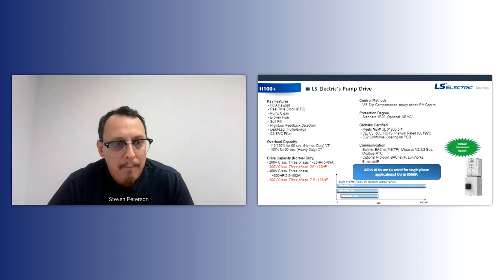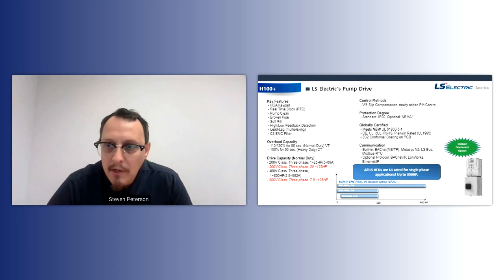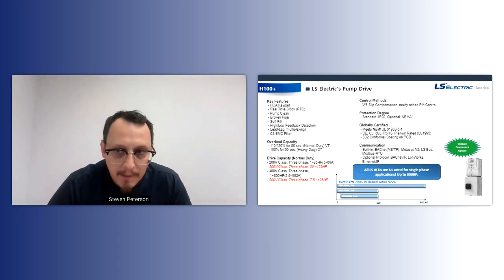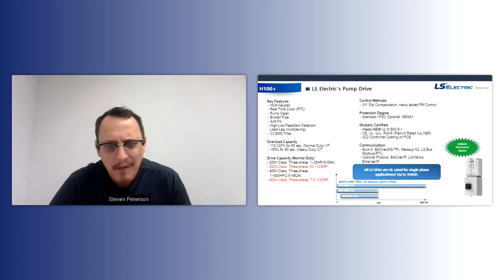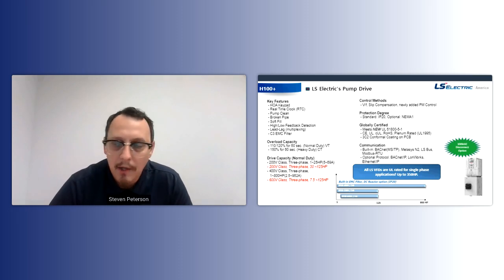Most pumping applications are going to be normal duty, 110, 120% overload for 1 minute. So you could overload it for up to 1 minute. You could also size the drive for heavy duty. That may be used on piston pumps or reciprocating pumps. If you get involved with compressors or similar equipment, that would be another application where we'd size the drive for heavy duty. So we could do either on this H100 Plus series drive.